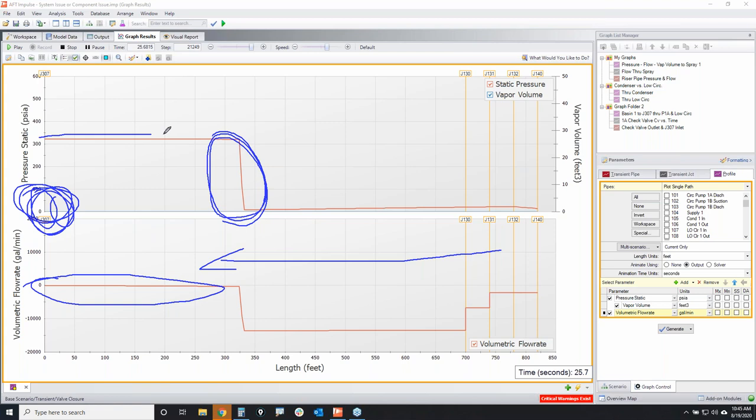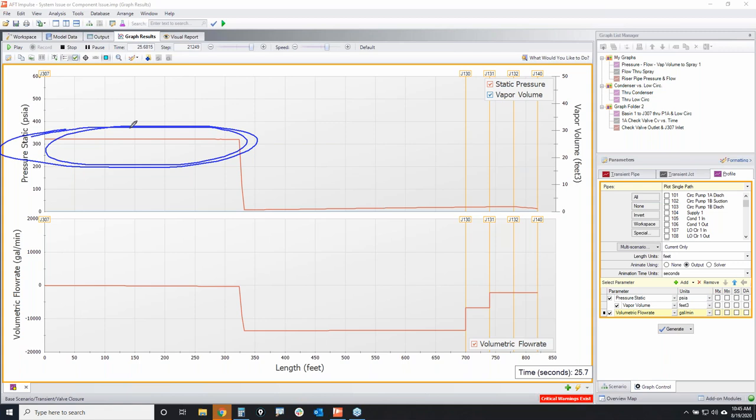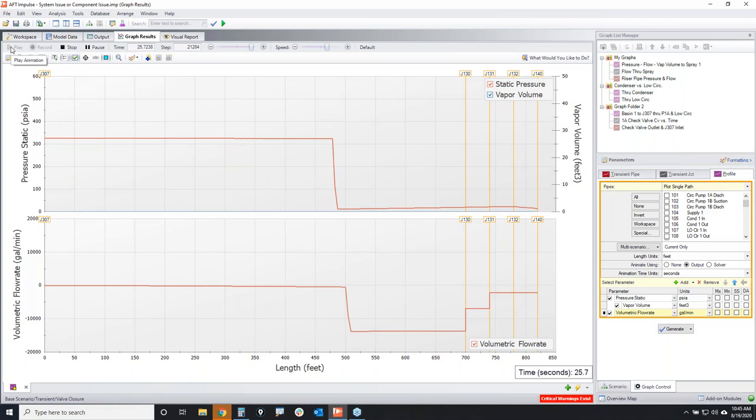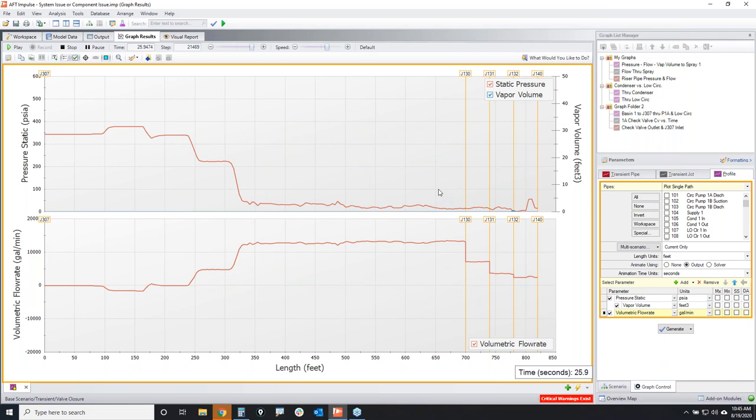But we don't have any liquid in the pipes anymore because the pipes are empty. And so this is an upper limit on that pressure surge that you would see. What's the real pressure in real life? Is this realistic? It's hard to say because your pipes are basically empty. Maybe there's a little bit of fluid. Maybe you start having some slug flow moving around in your system. The trouble is the mathematical calculations, it doesn't know. And so this is where you have to separate the math from reality to really understand what's going on.